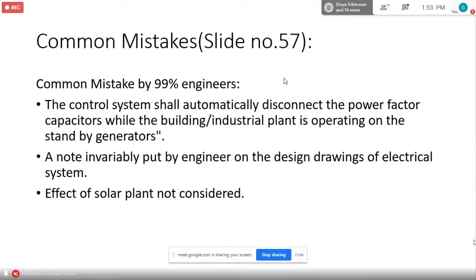Common mistakes by 99% of engineers. The control system shall automatically disconnect the power factor capacitor while the building or industrial plant is operating on the standby generators. I am sick and tired of explaining to engineers. You don't need that. Engineers think that the generator cannot handle these power factor correction capacitors.